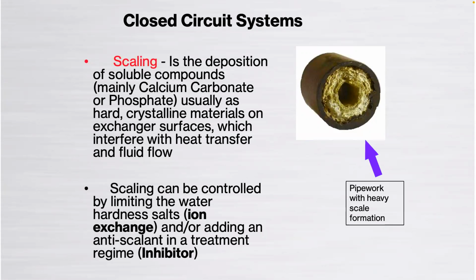So if you're in a hard water area, the only way to really manage scale and hardness in a closed loop system is either ion exchange, which is essentially water softening. I'm not a big fan, if I'm honest. I think water softeners could also be a risk, because water softeners use salt to regenerate, and if they don't rinse properly, you can end up with a huge amount of salt or chloride entering your system. Or an anti-scaling treatment, which is where your inhibitors come in. If you're using any kind of treatment, you need to make sure it's got a good level of treatment in the system to make sure that the scale will not precipitate out.